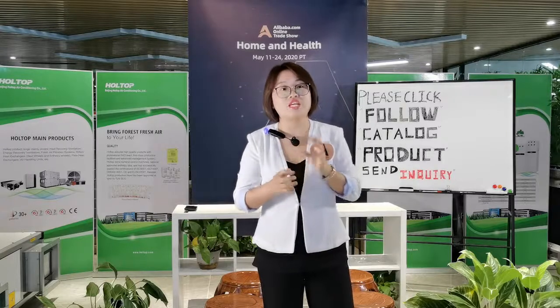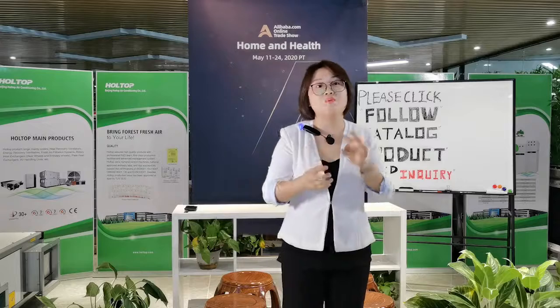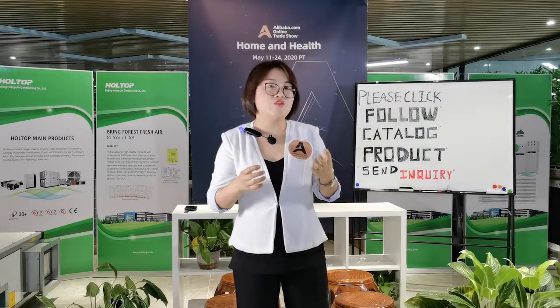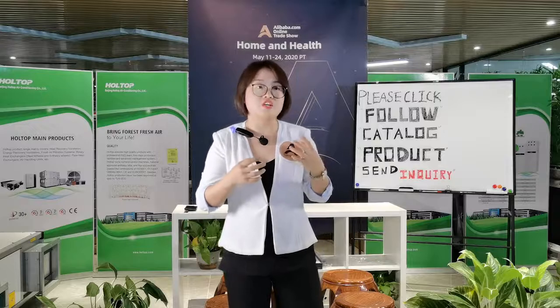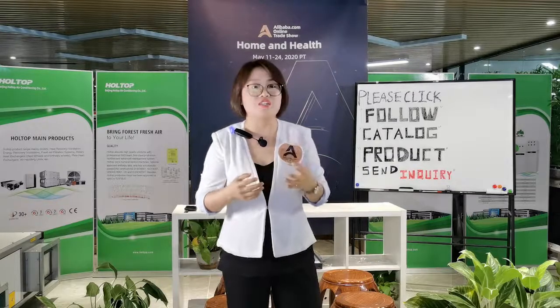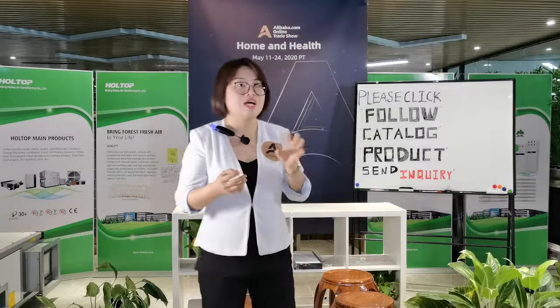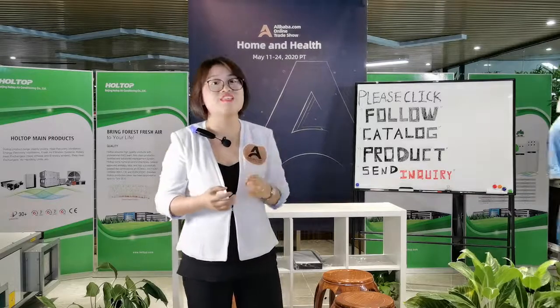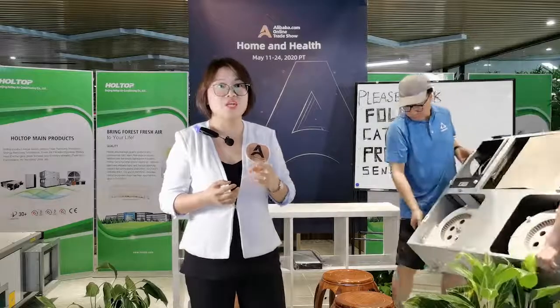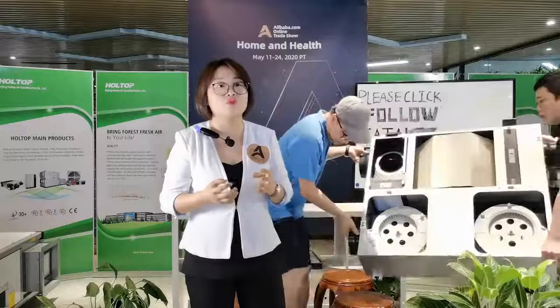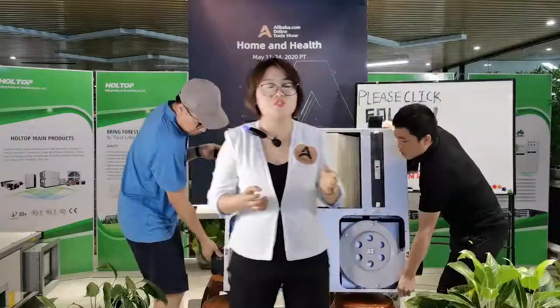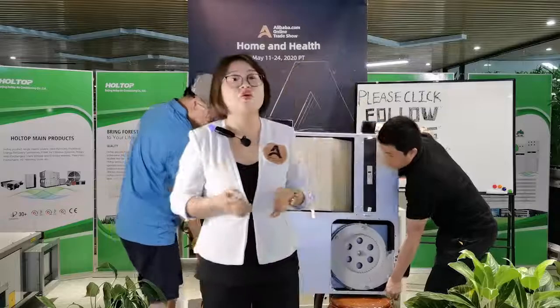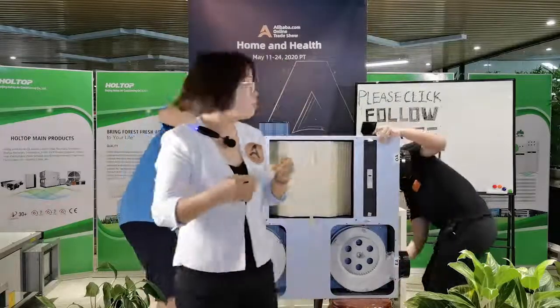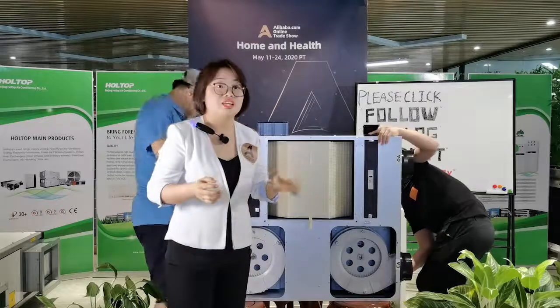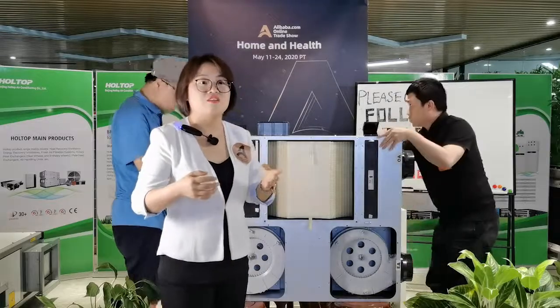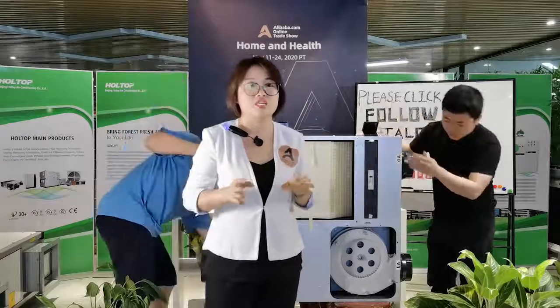Besides heat recovery, it also exchanges moisture, the humidity. To make it simpler: the HRV is built with a sensible heat exchanger, like the aluminum material core. The ERV is built with a total heat exchanger, like our enthalpy heat exchangers. So this is the most important difference between HRV and ERV.